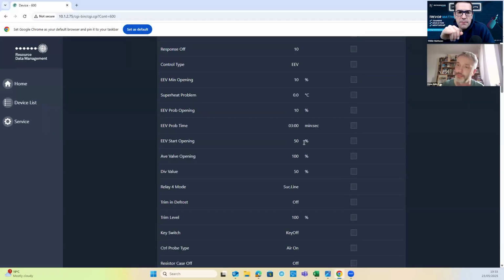So when does the minimum open? So on startup, right when the digital input closes, you go to 10%? So yeah, minimum opening is in normal operation, if your superheat is below target but not critically bad. That hasn't hit your low superheat number, which is your superheat problem number there. That's the minimum it'll go open to. Normally we would have superheat problems set, let's say 2 degrees C, something like that. If it gets below that limit, it's going to go into problem.